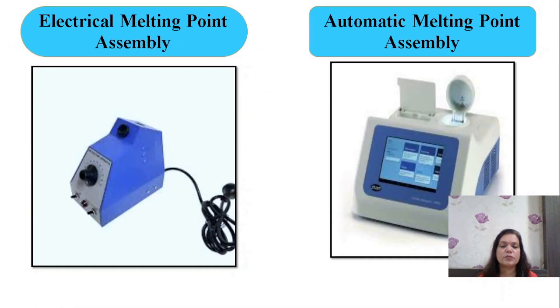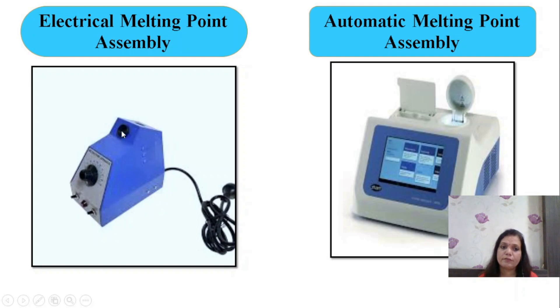These are the assemblies available in the market as an electrical melting point assembly, where you need to load the substance along with the thermometers. You just need to put the capillary along with the substance inside this assembly and apply the temperature at a constant rate. You can find out from the observation hole whether the substance has melted or not. This is an automatic melting point assembly.